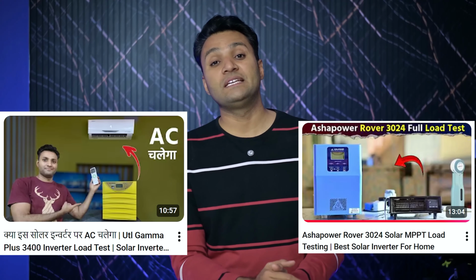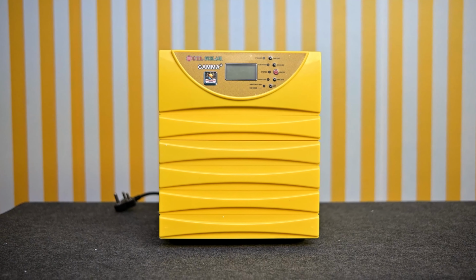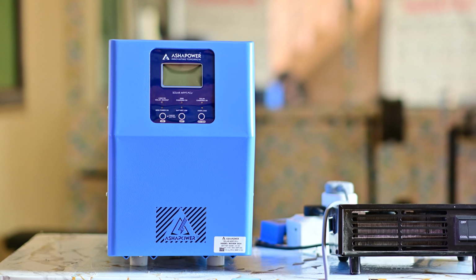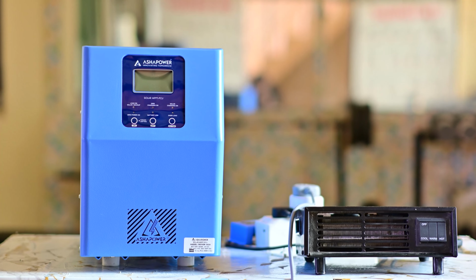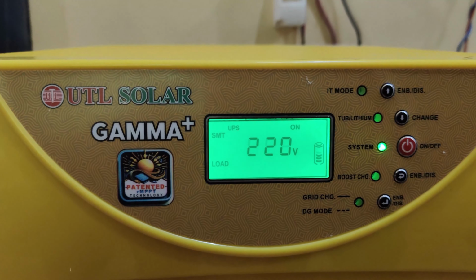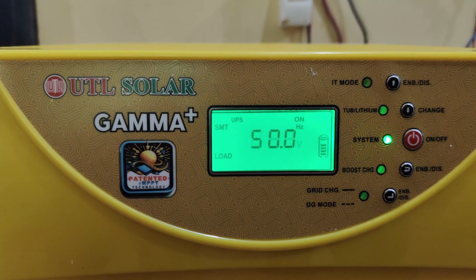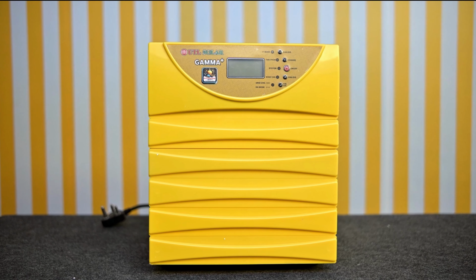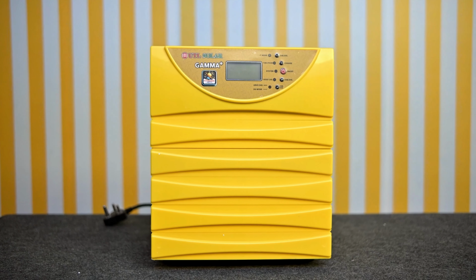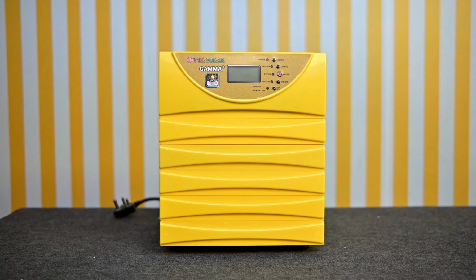We have tested the UTL 3400 inverter and also tested the 3024 model from Asha Power. Both are sold as 3 kVA inverters, but the Asha Power model costs around 40,000 rupees, while the UTL 3400 costs only around 18 to 20,000 rupees. During load testing, the Asha Power inverter was able to handle a full load of around 2400 watts. That means it was actually performing according to 3 kVA and 0.8 power factor. But the UTL Gamma 3400 model could only handle around 2 kilowatts load. So if you buy the UTL Gamma 3400 inverter by applying the 0.8 power factor formula, then your load may not run properly. That is why it is also important to see which company inverter you are buying and in what price range it comes.